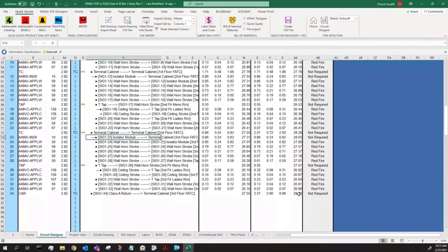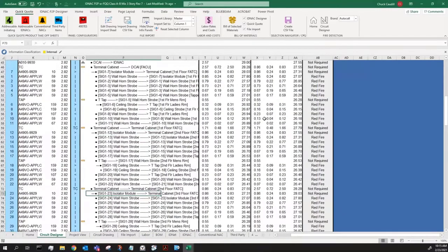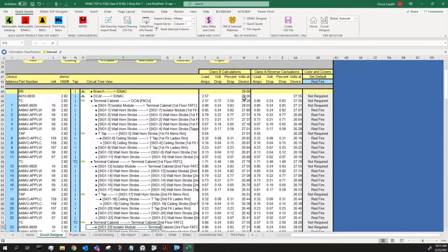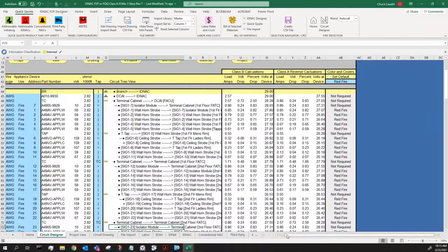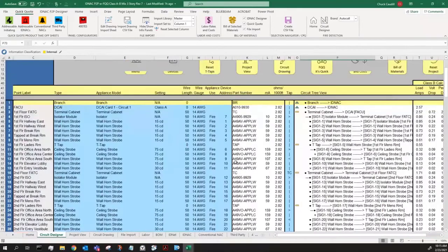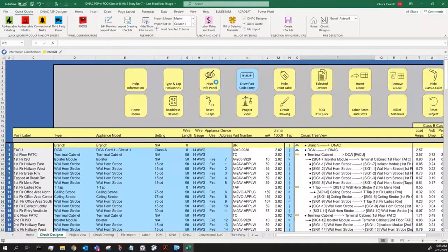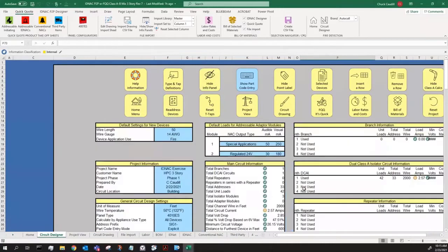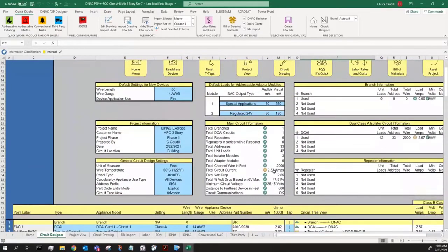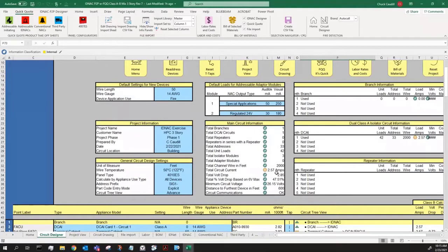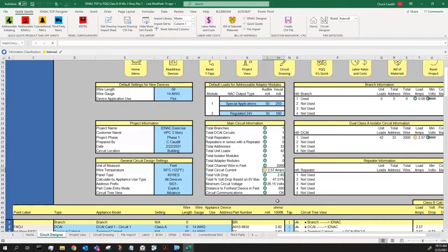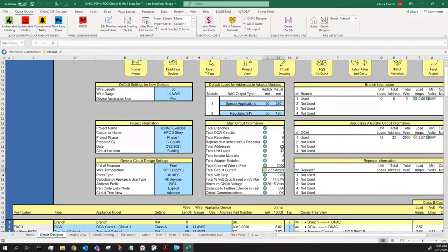29 volts coming on the Class A return, decreasing. 29 volts from the Class A out starts at the panel and decreases the further you get away from there. So my volts are good. What do my amps look like? If I open the info panel, I see that I've used 2.57 amps of my three. So I'm getting kind of near the end of the power availability. So it does show it in yellow, but I'm still within parameters. So I've used only 33 devices on this 127 point channel, but I'm out of amps.